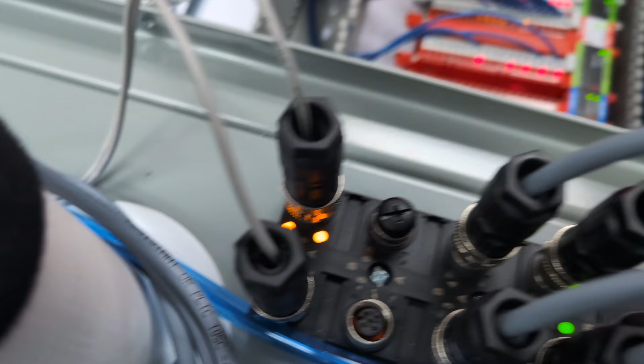Looks like my vibration monitor's got some lights going on. The encoder's got some lights going on. And yes, I know I need to do more than just be excited that the lights are going on, but let's face it, we all get excited that there are actually lights working, that we may have wired something correctly. So the next thing I'm gonna do is an actual IO check online with the PLCs.